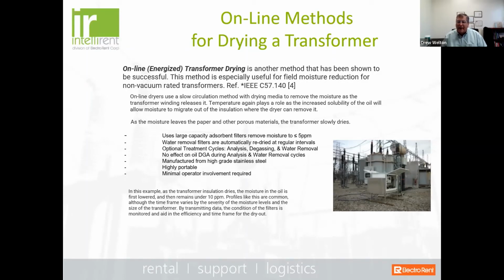Now, how does that help improve the process? Well, if your transformer is online and it's loaded down, that means you're going to be operating at a higher temperature, okay? Which means that at an operating temperature, you're more at an equilibrium state where your moisture in the insulation equals what's in the oil. So as we dry the oil under load, okay, what this does is it starts to pull the moisture out of the insulation to maintain equilibrium. And this is actually quite a benefit to be able to use these types of systems and to be more effective in pulling out the moisture.